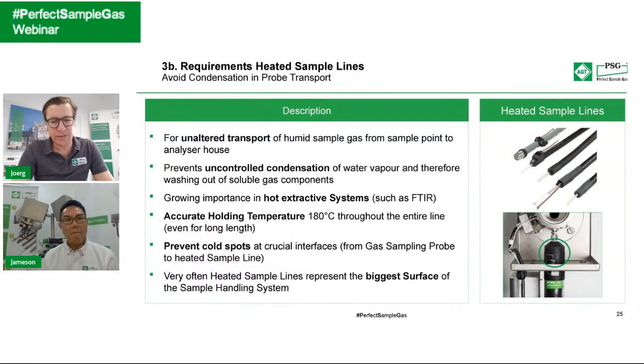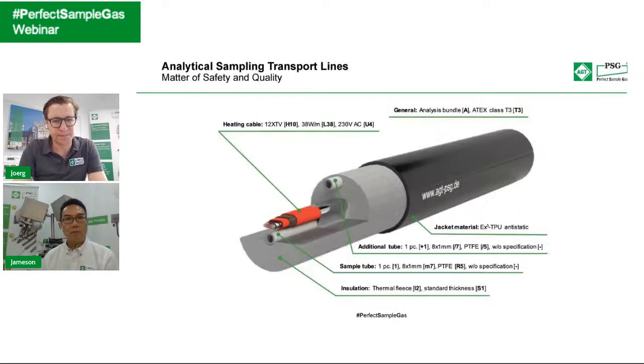Yeah, this is the spot we just mentioned. It's a crucial spot, the connection from the gas sampling probe to the heated sample line. And like we said, a common mistake, Jameson, could be that there is too much space in between, right? Correct, yeah. And that there's no insulation. So if there is no insulation, make it closer, cut the PTFE a little bit shorter, make sure the fitting is well connected, and then try to insulate as much as you can. Always, or sometimes, this can be a potential crucial point for creating condensation. Yeah, yeah.